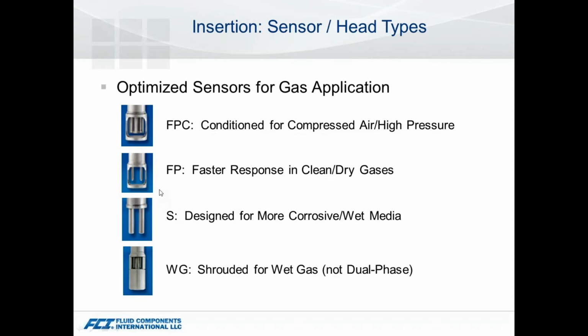The F-style sensor, a little bit thinner thermal well, gives you a little bit better response time than the S-style sensor, which has a thicker thermal well and is more designed for when you have some H2S, some other corrosive medias that might be slow acting. It gives you a little bit more mass to deal with in that thermal well itself before there's concerns about replacement. For the thinner thermal well items, you can see they've got protective cages around them.